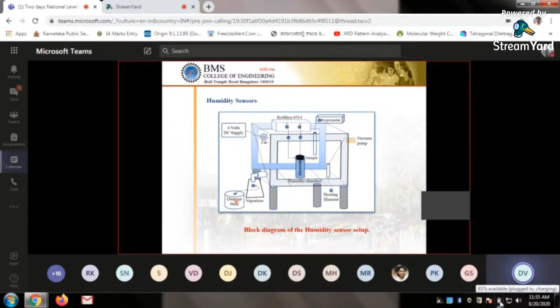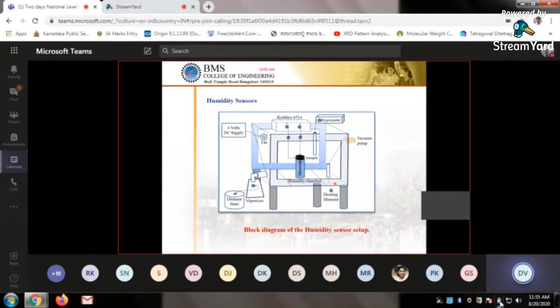We have a hygrometer to measure the humidity of the inside temperature, and we have a thermostat at the vaporizer to increase the humidity inside the glass. A simple setup, and this is how it looks. It's an actual photograph of the simple humidity setup that we have set up in the lab. And what we observed: if you plot a graph of resistance and relative humidity, as humidity increases, resistance decreases.